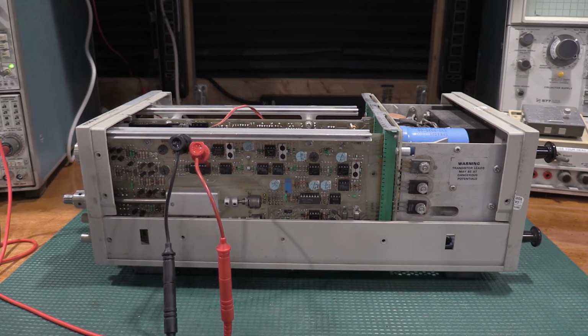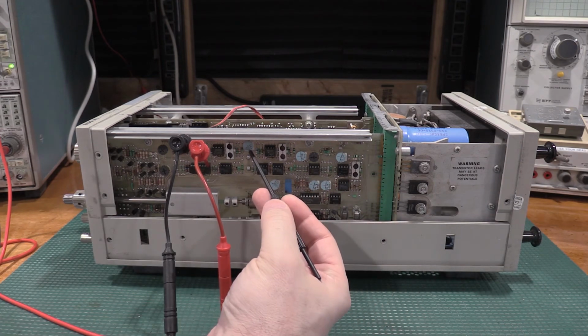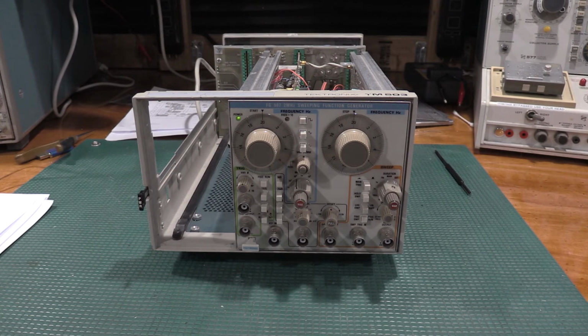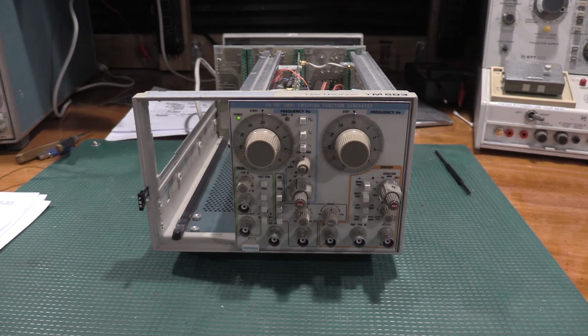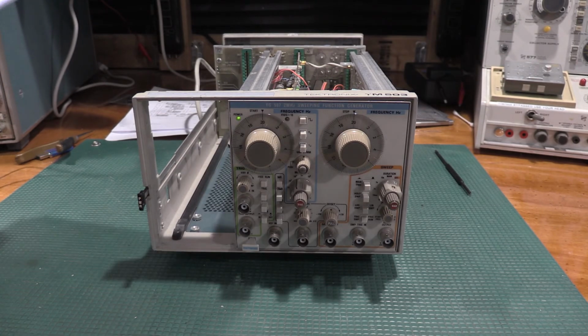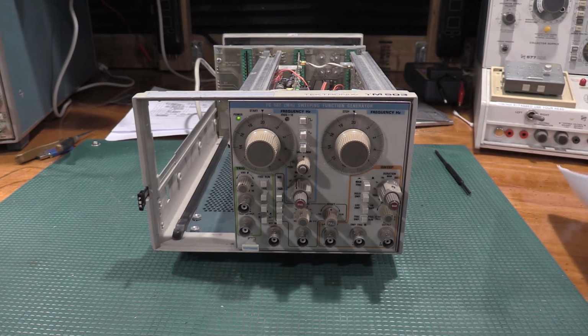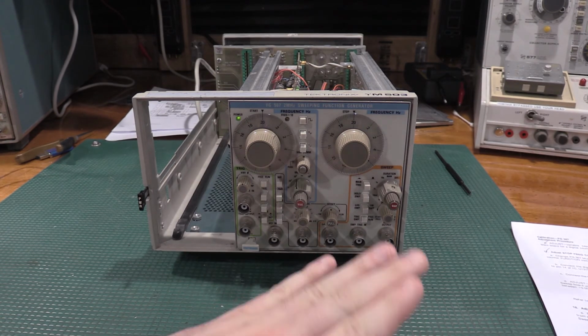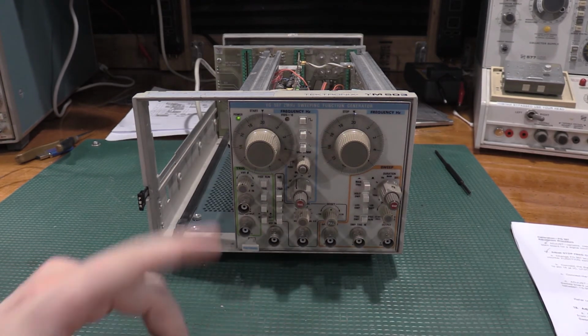Exact same adjustment, except now we're adjusting 1503, which is right here. Okay, given the start and stopping, I got the step 19 done. 1503, it's the same thing as step 18. But part of my confusion there was the general setup of the frequency counter, because I had it confused, so I redid step 18 and 19.